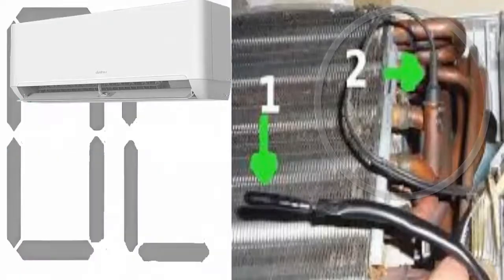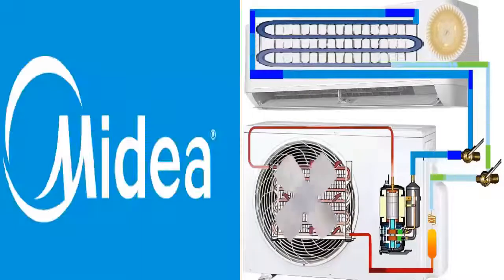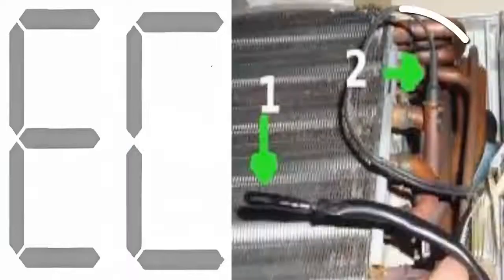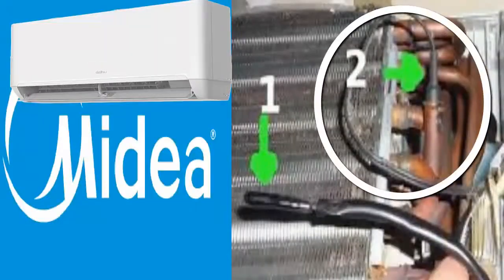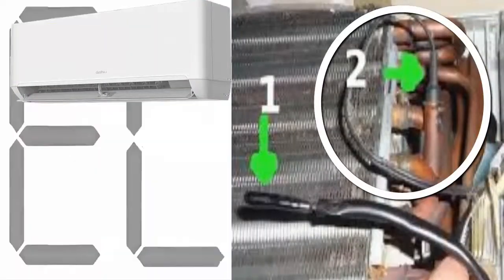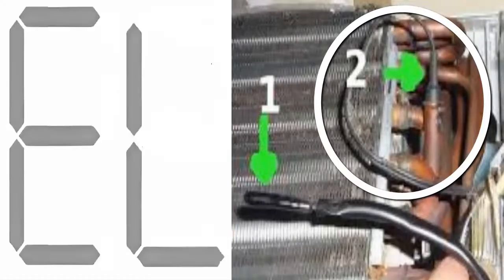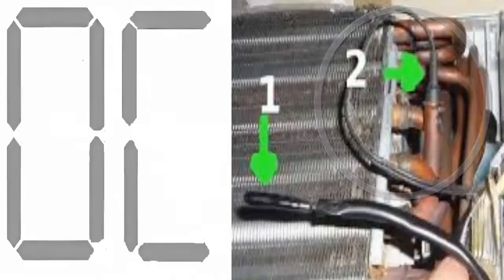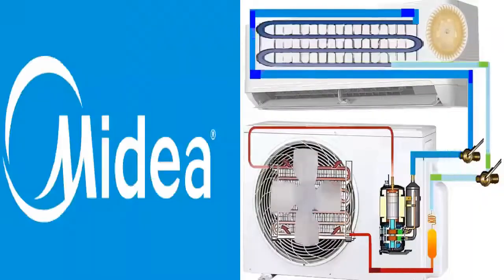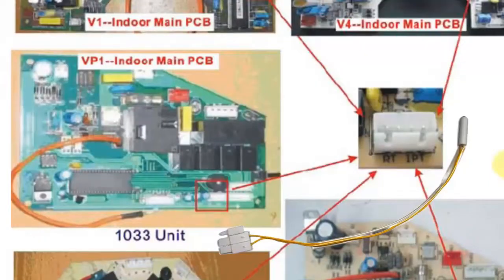Step 5: Check the correct position of the sensor and the condition of the wires from the electronic board to the sensor. Step 6: If the error persists, turn off the unit, disconnect the sensor, clean the connections, and reconnect it.